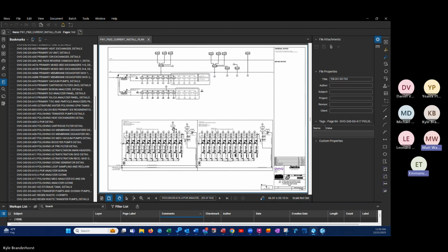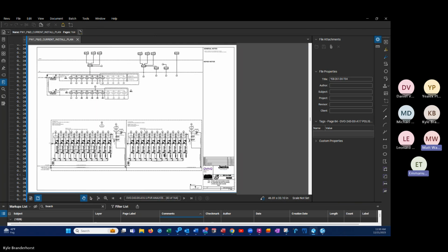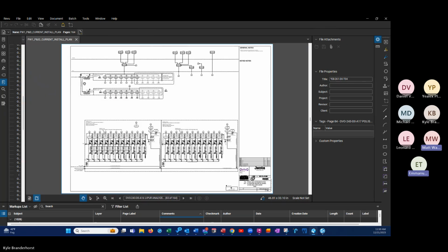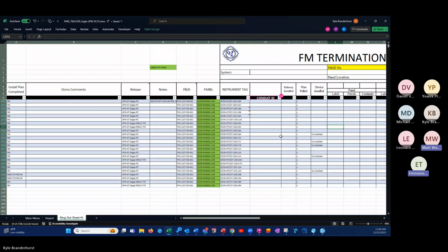So, question for Matt. I got the X on this, updating the folder and making sure some of them I pulled X as wire pull, but I think I probably need to go back in there and put notes, because for some of them there is no wire to the FE yet, and some of them don't have a conduit. So I guess I can just go ahead and put that as a note, right? That way anybody who sees it can see that wire is pulled to the main devices, but the jumper is not pulled yet, right?